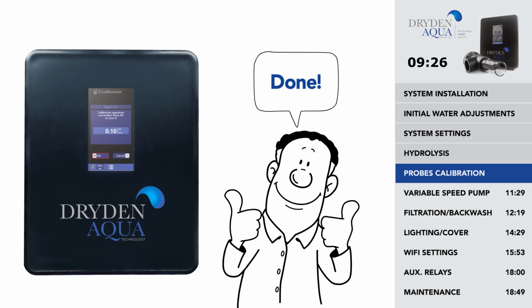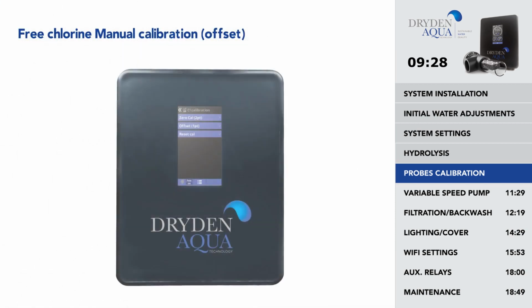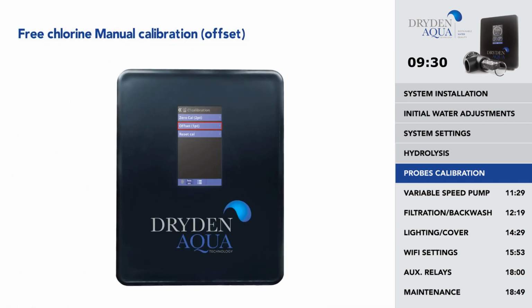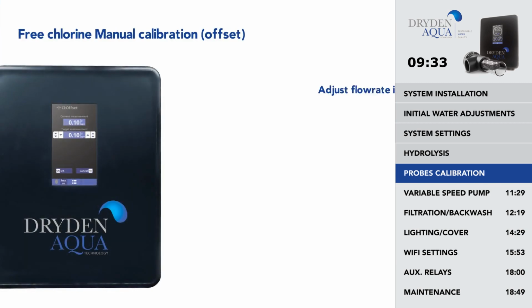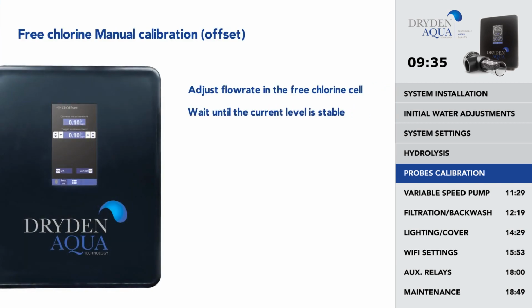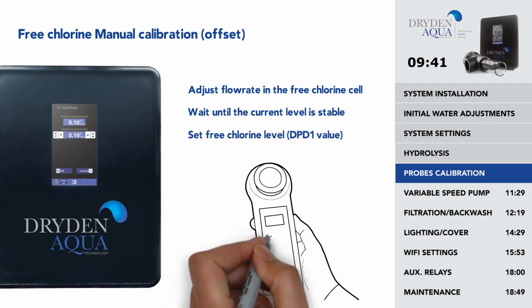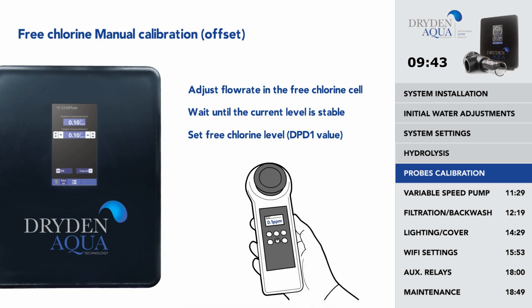If you want to calibrate the free chlorine probe manually, open the water flow, set flow rate between 50 and 100 liters per hour, and wait until there is a stable reading. Then, use your photometer and DPD1 test kit and set the chlorine level with the up and down keys manually to match your photometer's reading. Press OK when the value is correct.